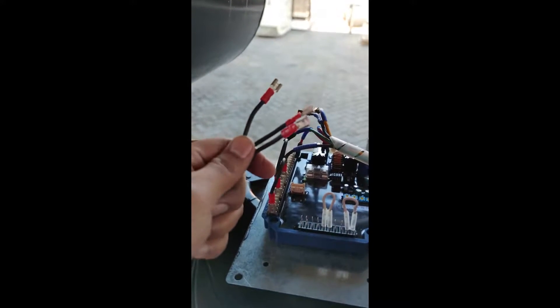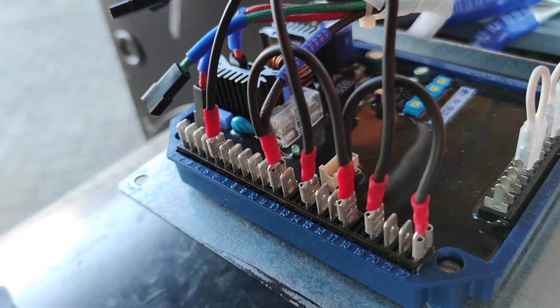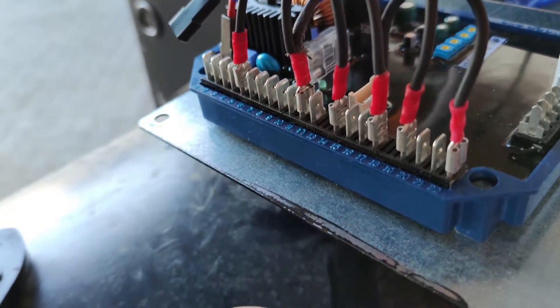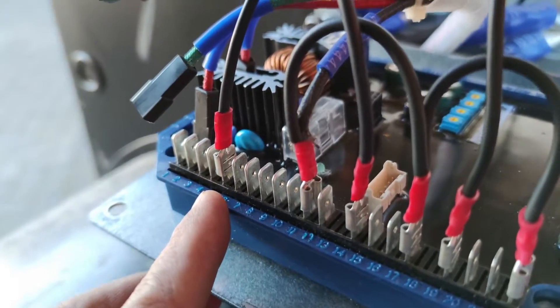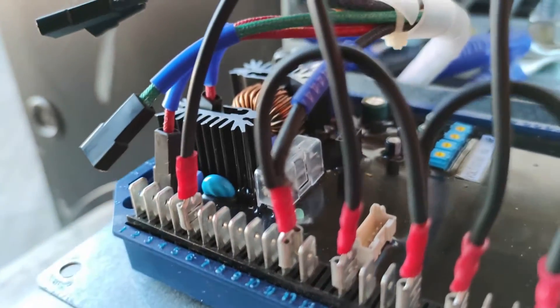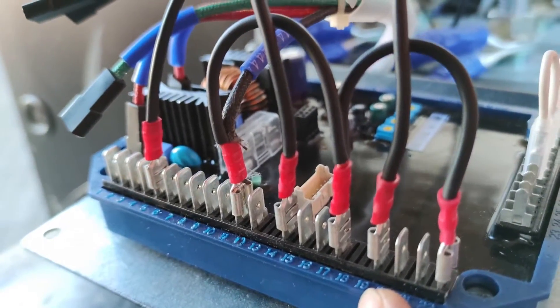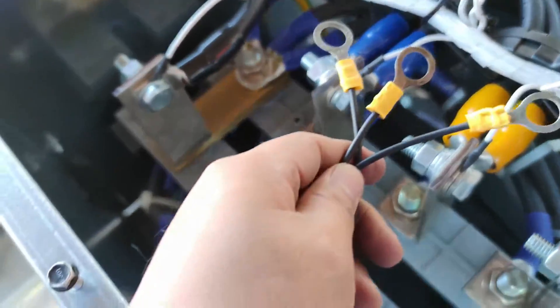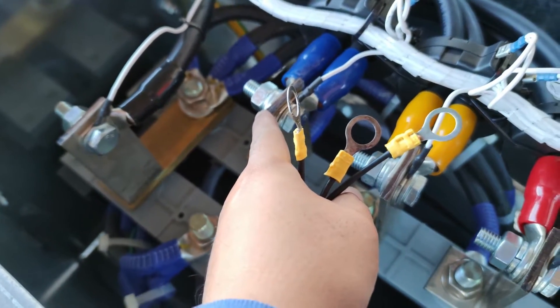I'll prepare also for our three-phase sensing connections. This is the three-wire that I'm going to connect to our line and to the AVR. Here are the connections from our sensing line — we're going to connect from pins 5, 14, and 19. Those three cables connect to line one, line two, and line three.